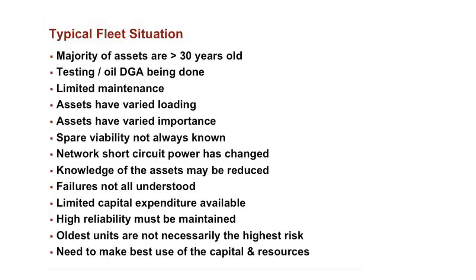And usually most units are having testing done maybe every 3 or 4 years, oil DGA is being done every year. Now, maintenance, some facilities have a lot of maintenance done, some facilities have less maintenance. If you look across the different assets in a utility base, some of them are heavily loaded, some are lightly loaded, and some are more important. And what I mean by that is some of them might have a spare unit easily accessible, or if they fail, it's not the end of the world. Other ones, if they fail, then it has a huge disruption for customers. So this is very important to know when you're doing a condition assessment.